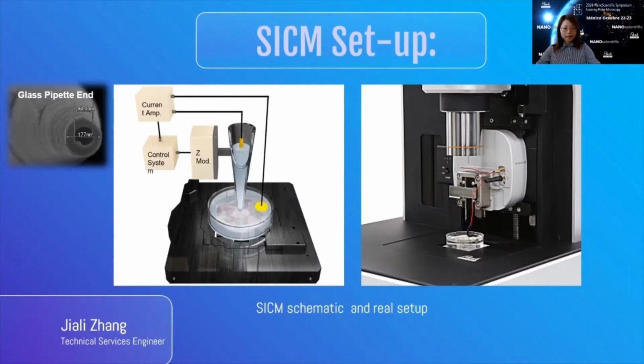In Park SICM, the AFM Z scanner accommodates the glass pipette probes in a similar way as it would a silicon cantilever probe. However, unlike the conventional AFM feedback mechanism, which is based on light deflection at the probe, in SICM the Z scanner responds to an ionic current flow through the nano opening in the pipette. The operator inserts an electrode into the pipette after filling it with an ionic solution. A secondary base electrode connects to the immersed sample, completing the circuit, and the voltage bias is then applied.